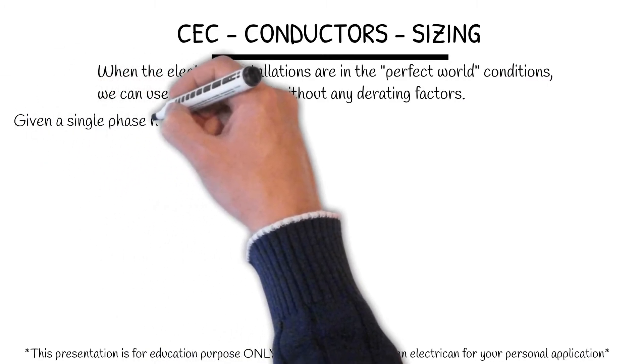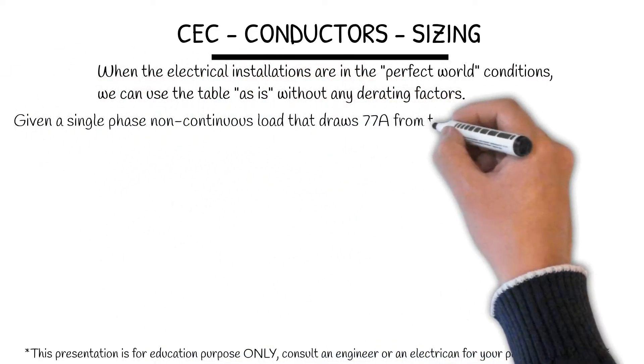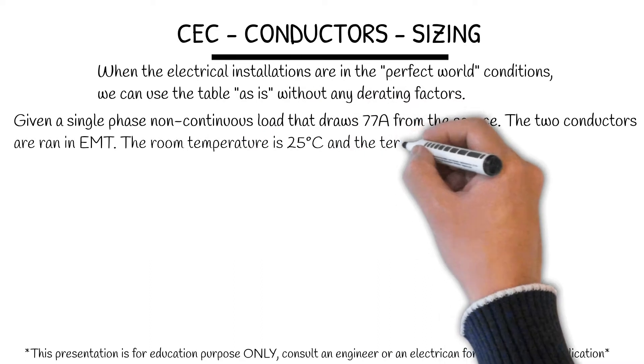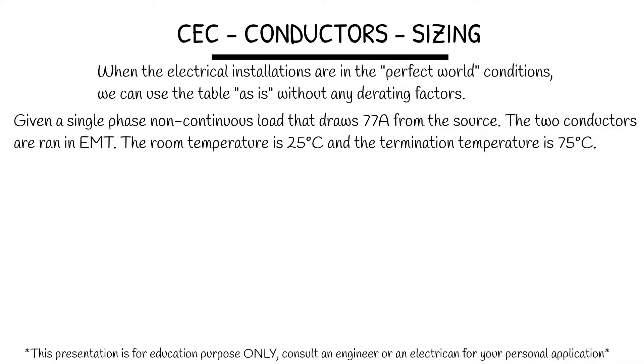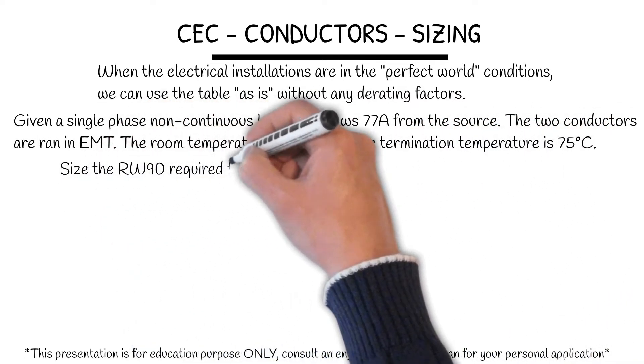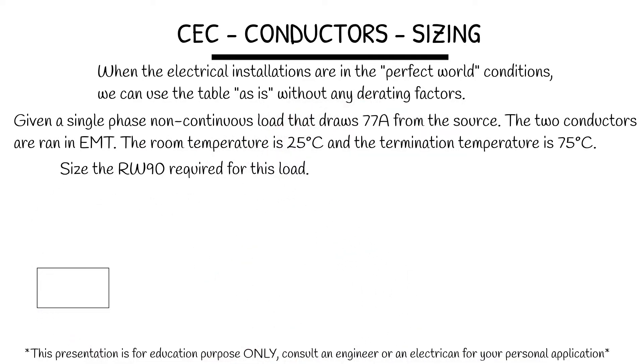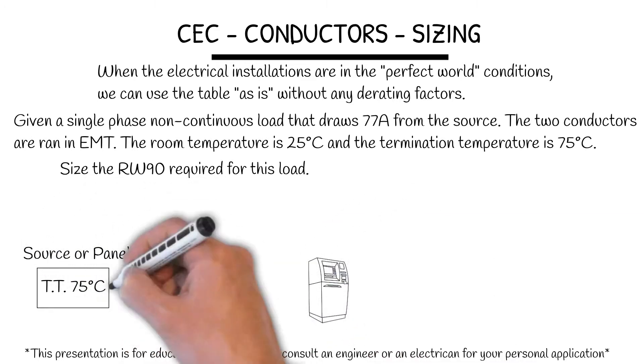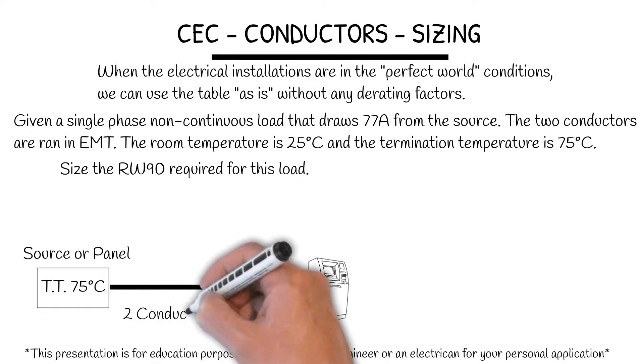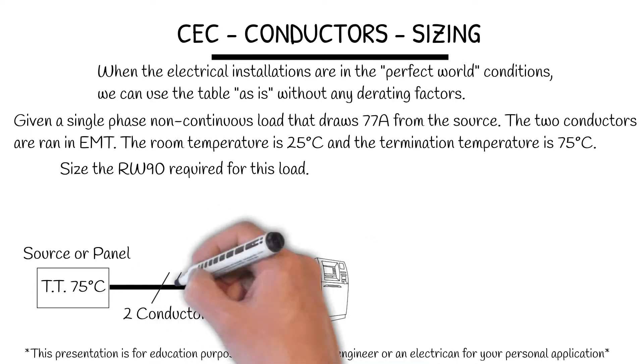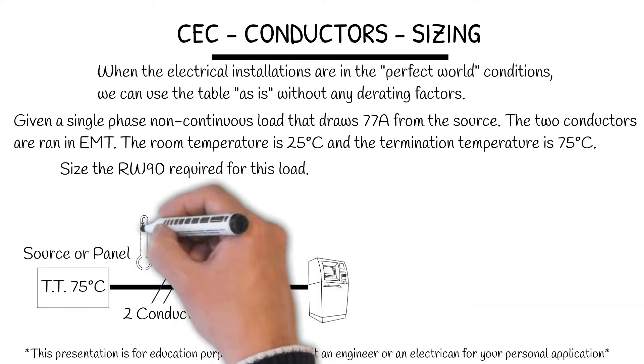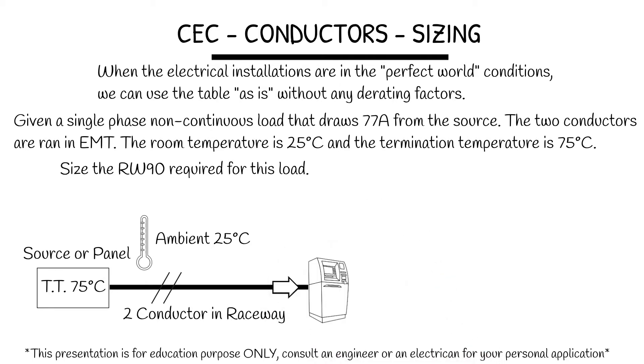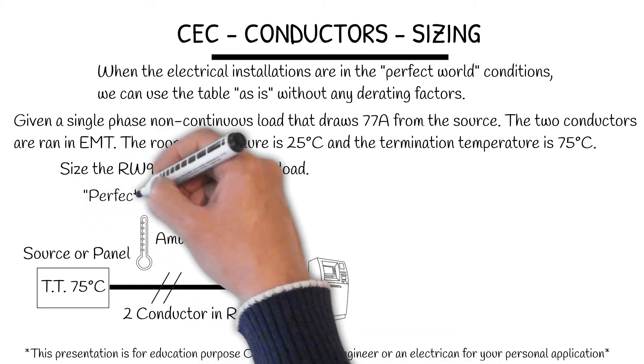Given a single phase non-continuous load that draws 77 amps from the source, and the two conductors are RW90 in EMT, the room temperature is 25 degrees Celsius, and the termination temperature is 75 degrees Celsius — so we have perfect world conditions. Size the RW90 required for the load. We have a termination temperature of 75, two conductors in the raceway, ambient of 25 degrees Celsius, and my load draws 77 amps. This is my perfect world condition.